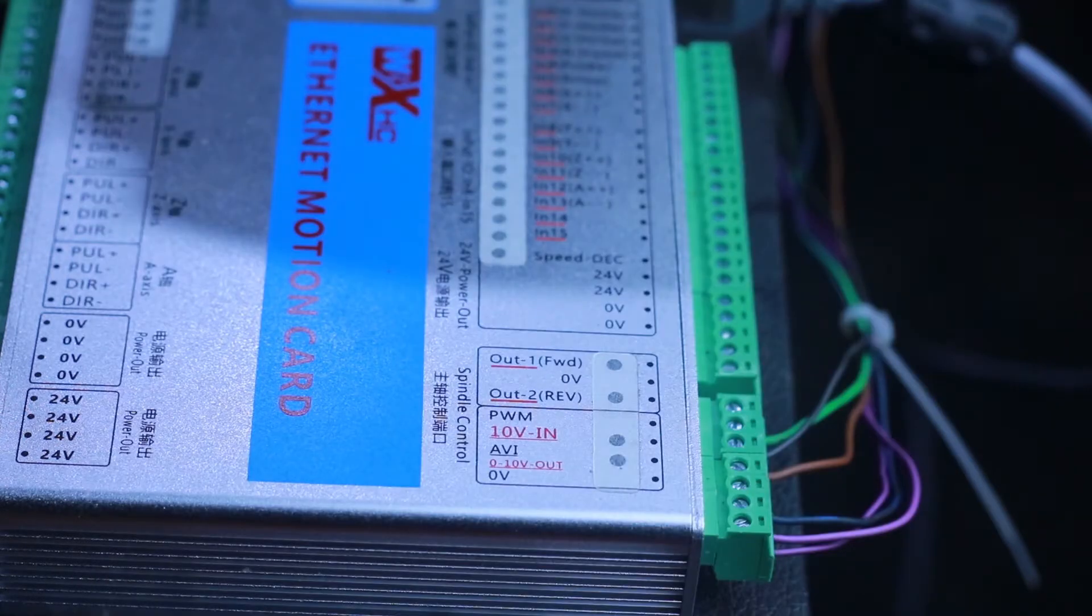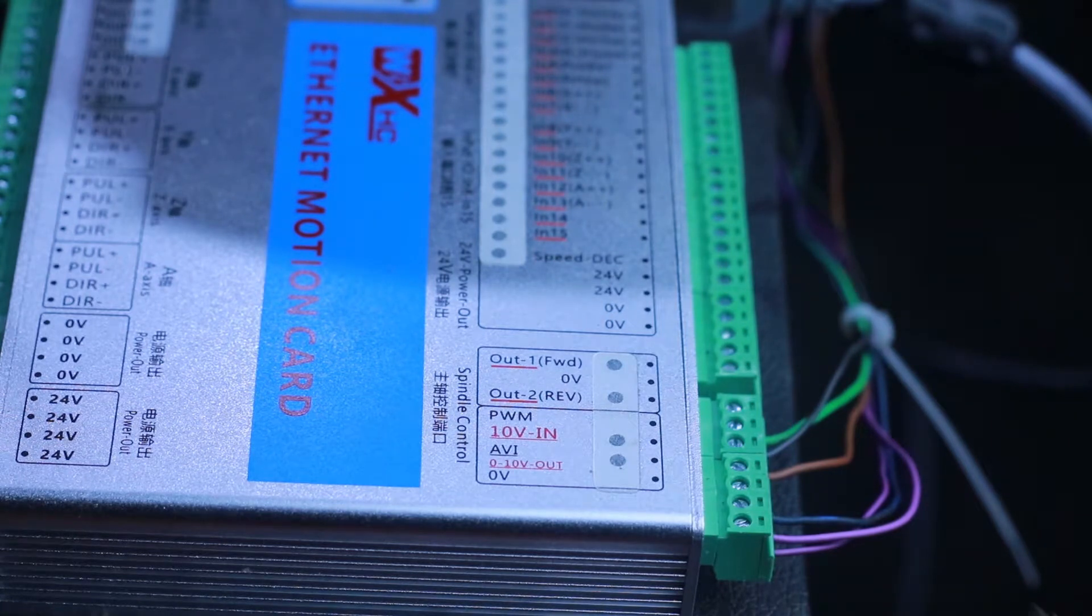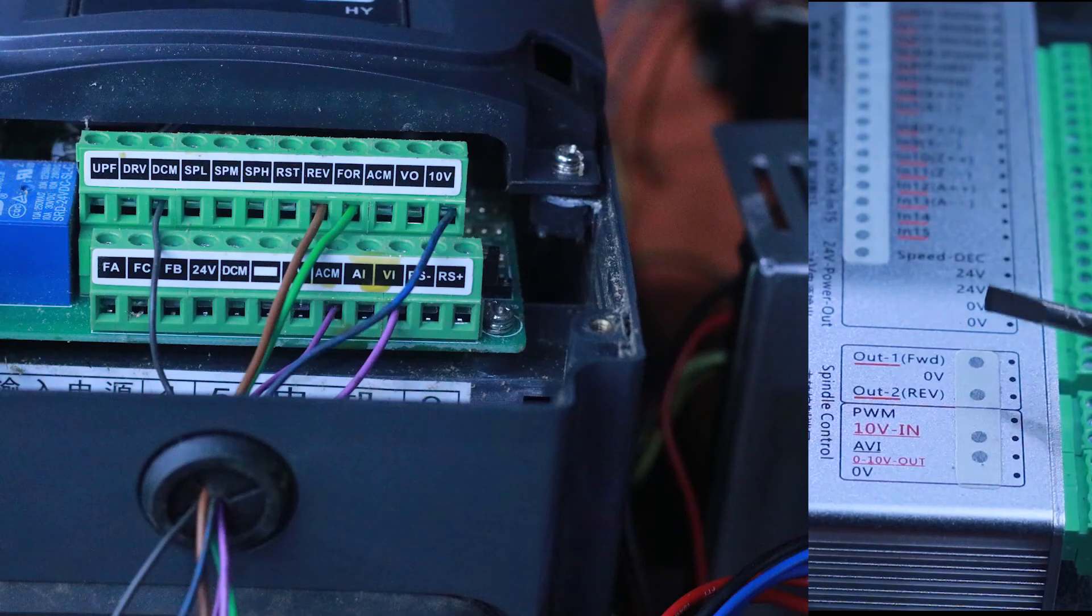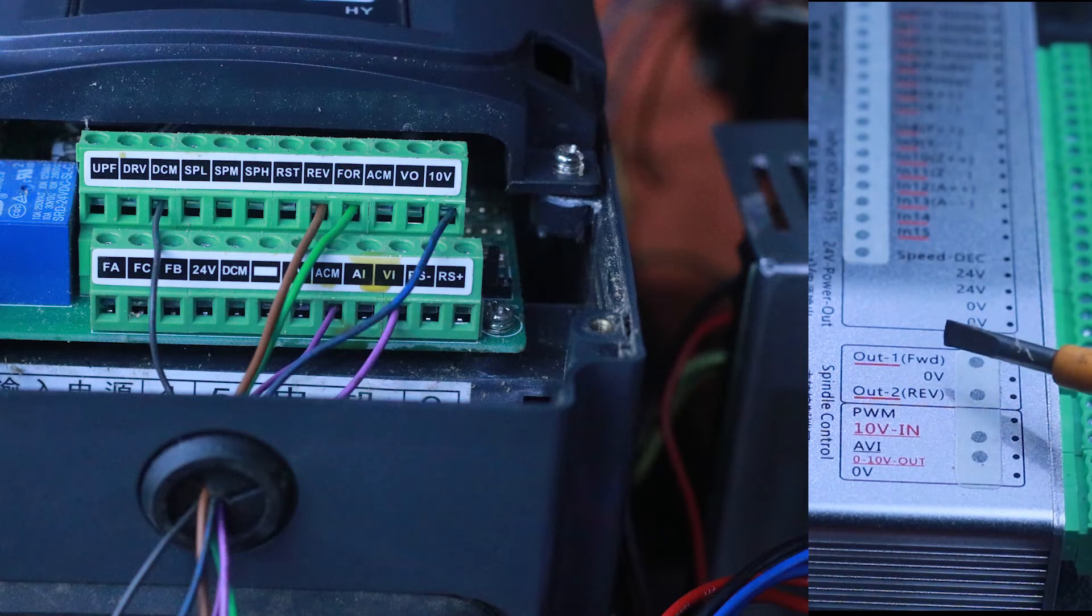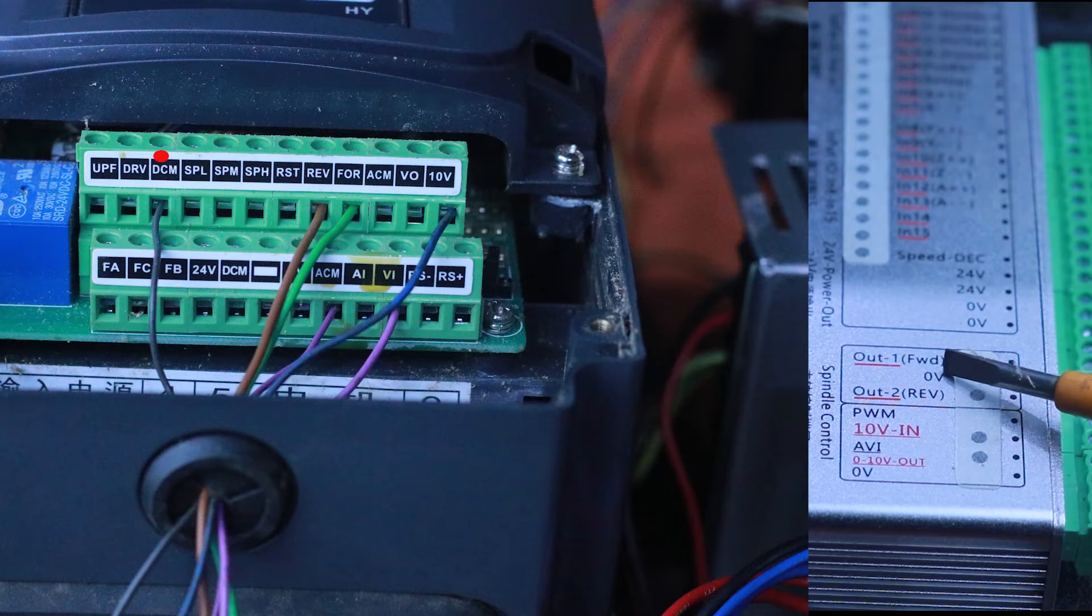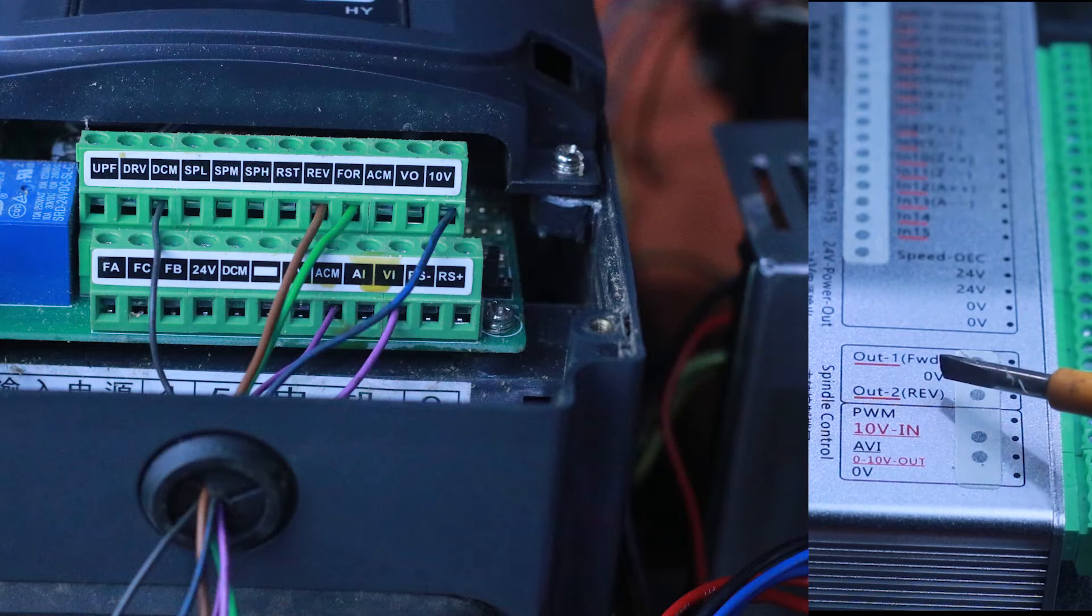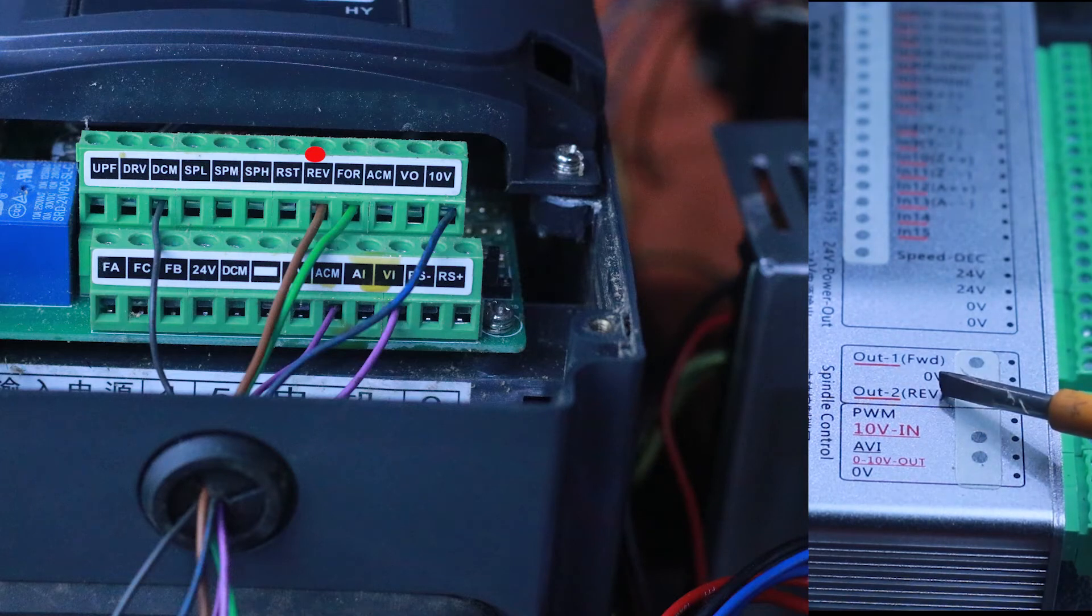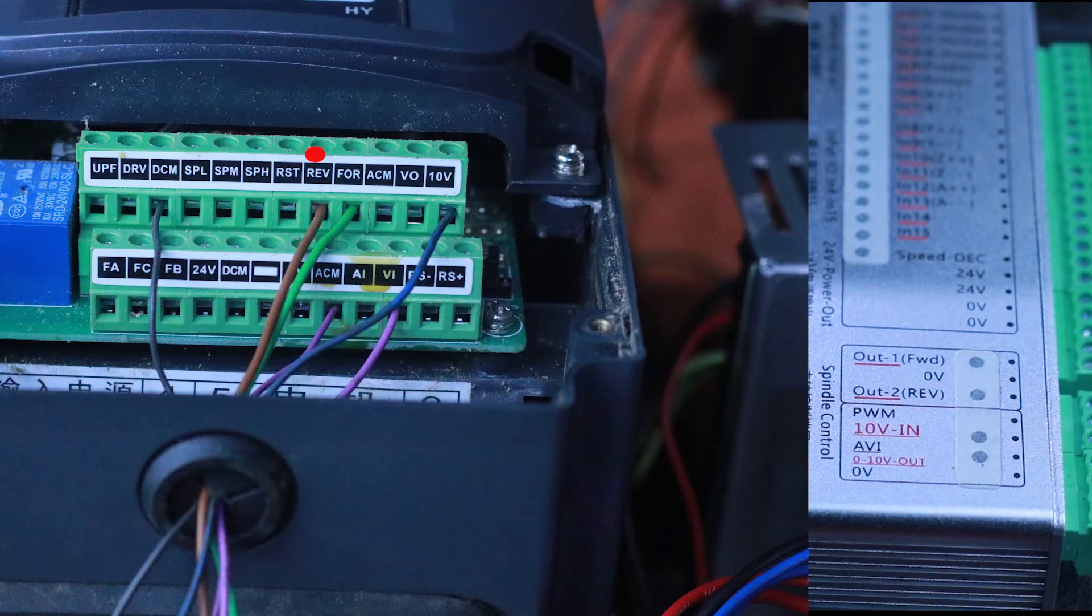We are going to connect them following that particular procedure. Forward goes to forward on the VFD, the digital ground goes to DCM on the VFD, and the reverse—this normally is not supposed to be connected but I connected it to the reverse of the VFD.